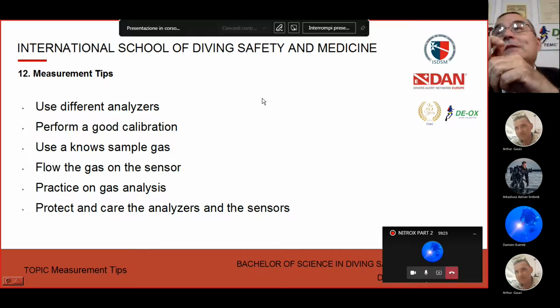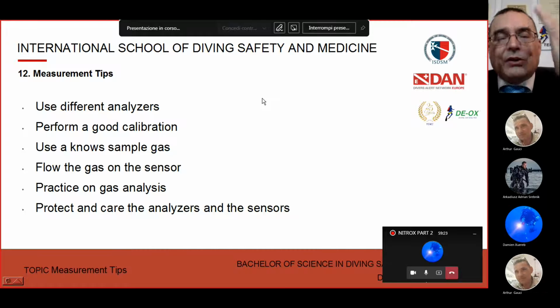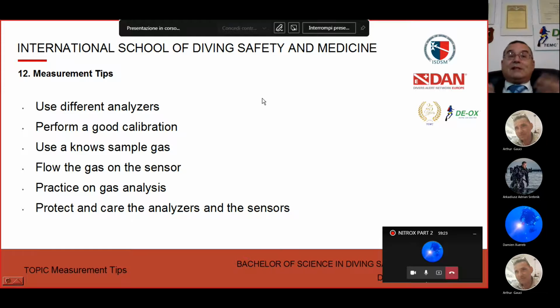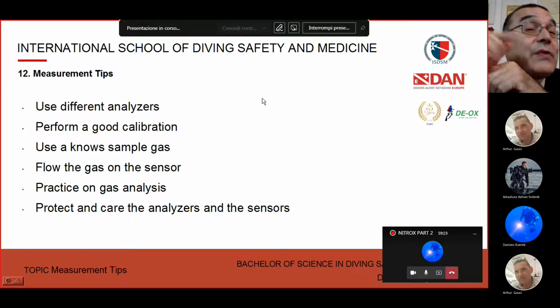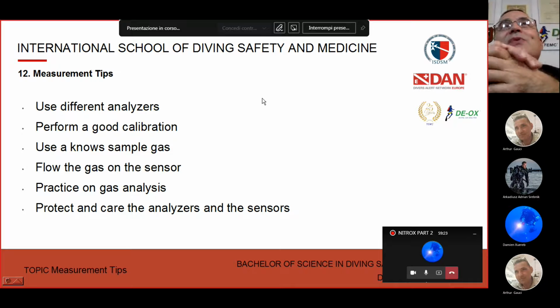Also use a known sample gas. That may scare you - you might think you have to buy a cylinder of sample gas just for this. Between you and me, a cylinder like the one I showed you costs around 300 to 400 euros, and to get one you need at least 2 months, because the preparation of sample gas is very long. They do the analysis, then let it sit and wait for balancing inside, especially for very low concentrations. For instance, if you need a calibration gas for 5 ppm of carbon monoxide, that's 0.0005%, or isobutylene at 0.5 ppm, it's crazy how much time you need. The gas supplier needs time to provide it, the laboratory needs time to prepare it.